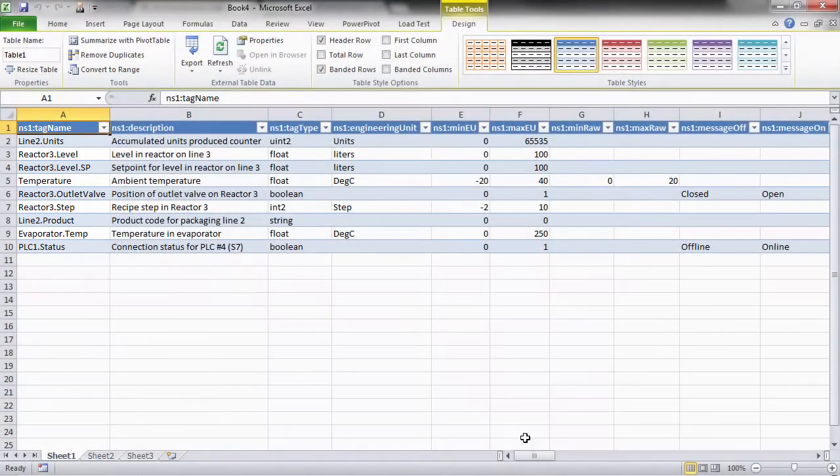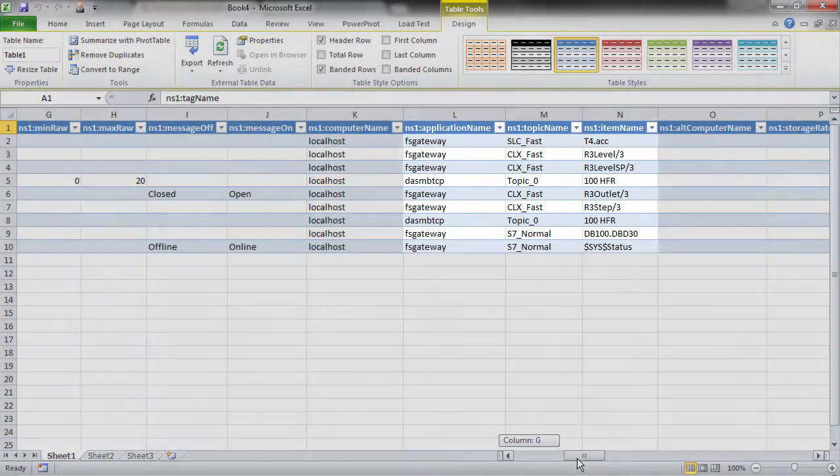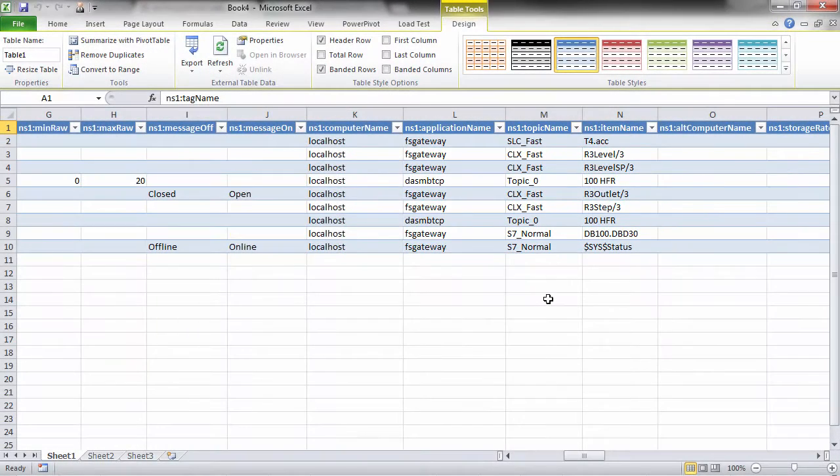Then I also have to make sure I get the subscriptions to the OPC item set up correctly with the application name, FactorySuiteGateway, the topic that I'll configure, and the actual item name in the OPC server.